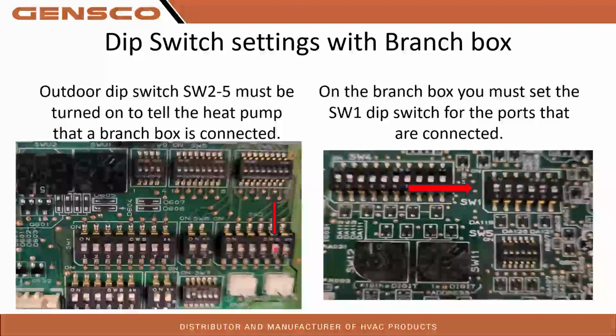on the heat pump, this is the only dip switch you will need to turn on if you're using a branch box. So I'm not sure how many old school guys we have in here, but we used to have the PUMYs and the 8C outdoor units. They were the same outdoor unit. The difference was this dip switch right here. So City Multi equipment versus branch box.